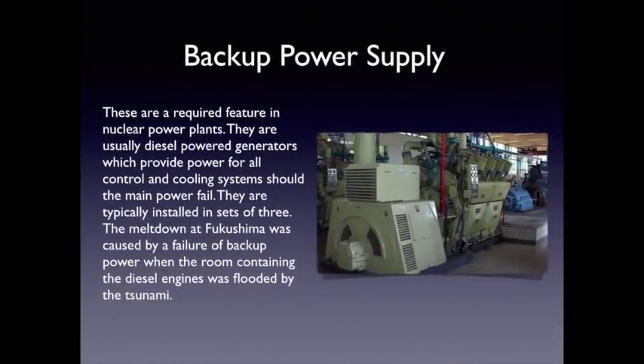The last feature common to every nuclear power plant is the backup power supply — one of the primary safety systems. They are usually diesel power generators providing power for all the control and cooling systems should the main power fail, and are typically installed in sets of three, so that if any one goes down, two are available to back up the power. The meltdown at the Fukushima nuclear plant in 2011 was caused by a failure of the backup power when the room containing the diesel engines was flooded by the tsunami that came after the earthquake.